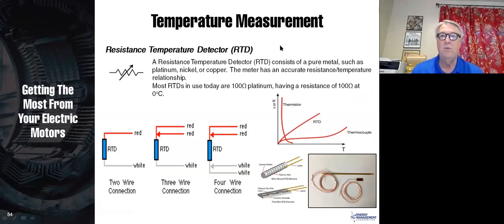This is a resistance temperature detector. So this just says that metals will have higher resistance at higher temperatures. And you could have iron, or you could have copper, you could have nickel, but what I see mostly these days is platinum. So the kind of standard that we see is 100 ohm platinum, which means that it measures 100 ohm when the RTD is at 0 degrees centigrade.